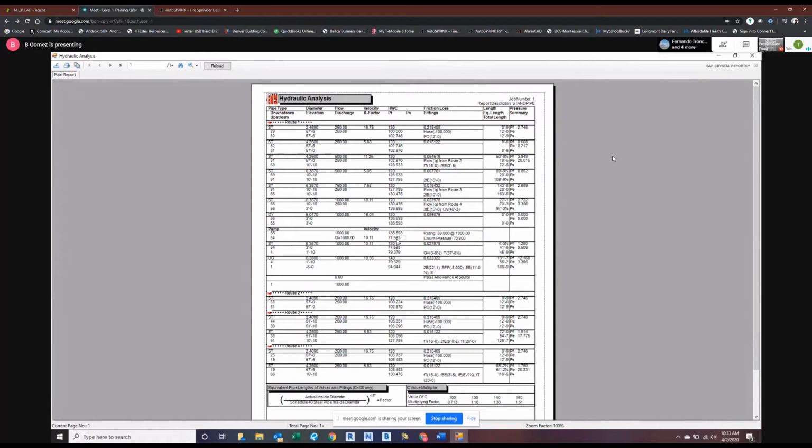And then it continues to compound pressure from that point back to your supply. So from your pump back to your supply, you're losing 12, 13, 15, 16, almost 17 psi accumulating. So this has all of the relevant hydraulic data that your pump guy would need to hopefully understand why this pump is not sized correctly for the demand.